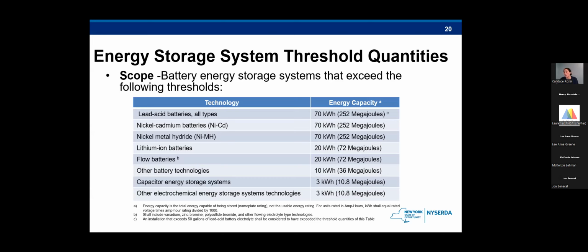If the system is in a group R3 or R4 occupancy, they shall comply with section 1206.18. But basically the purpose of this is showing that any lithium ion battery over 20 kilowatt hours will have to meet all the requirements we're about to set forth.